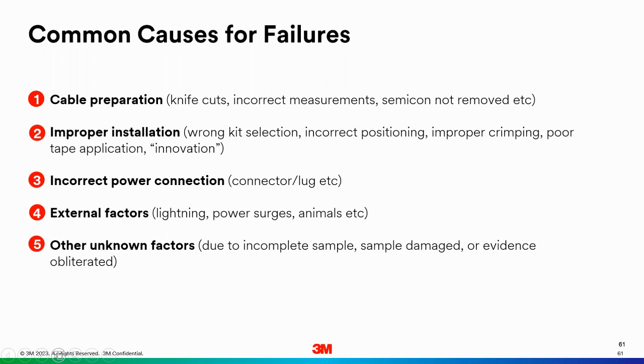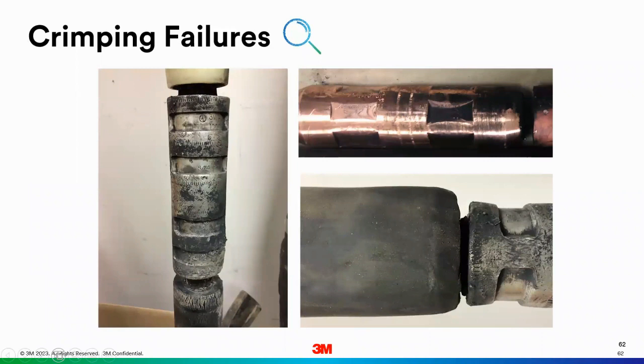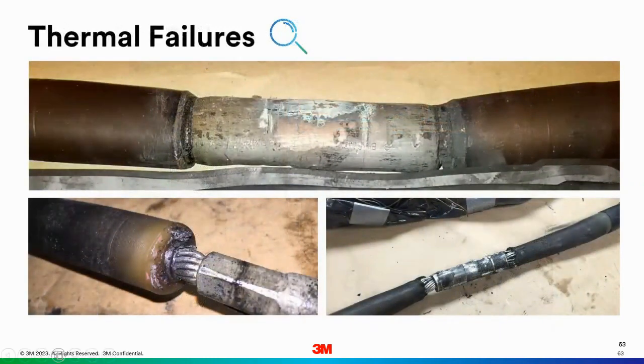And more often than not, it comes down to the cable preparation or the improper installation of the accessory itself, meaning not following the right measurements, or improper positioning, improper crimping. So in the next couple of slides, you'll see, for instance, in this one, this was improper crimping, and also crimps not rotated correctly, as you're supposed to rotate as you go down the lug or the connector. This one was just crimped with the wrong size die, eventually leading to thermal failure.